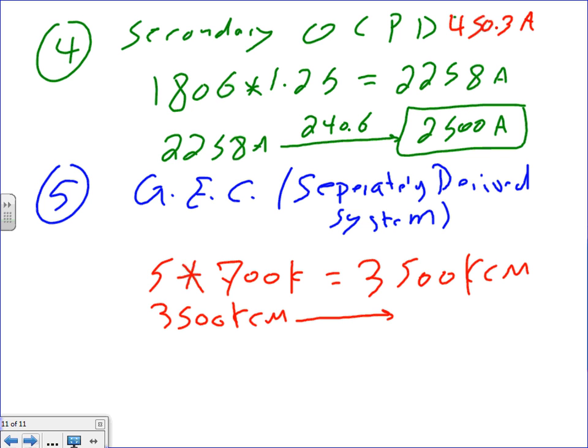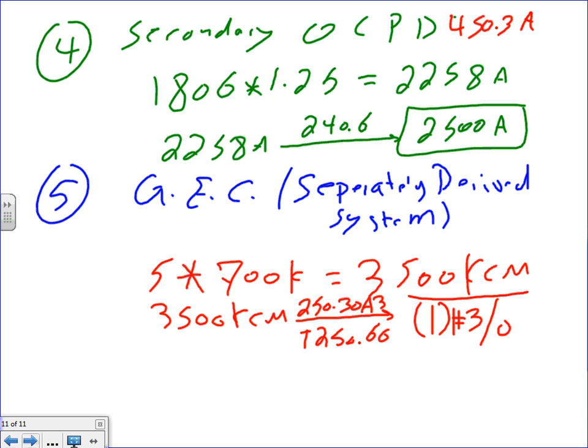Give me the reference, what was it, 250.30(A)(1), I think, or (A)(3). A3. And that will move you to Table 250.66, and that will get you, no matter what you do, don't even dream of it, 3 aught. Now, one conductor, 3 aught, for the grounding electrode conductor. So no matter what you do, you're stuck with a 3-aught grounding electrode conductor. The system bonding jumpers will be separate, different. Okay, so that's my 3-aught.